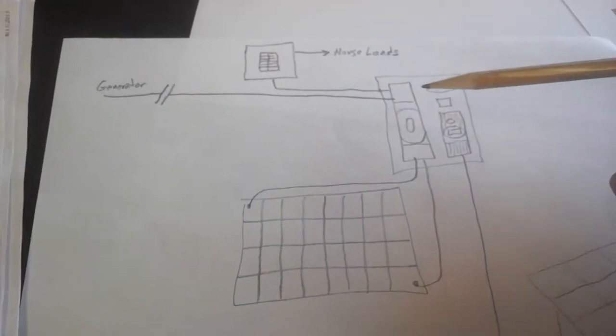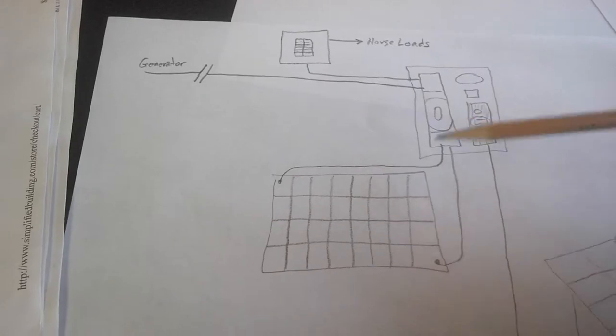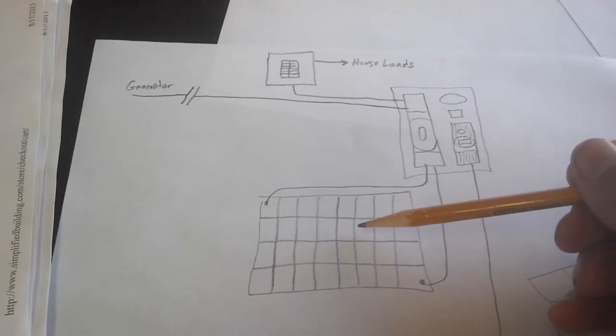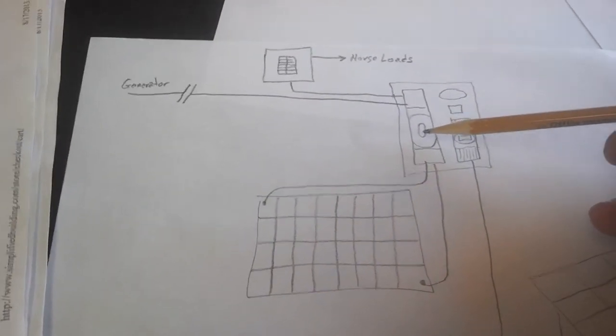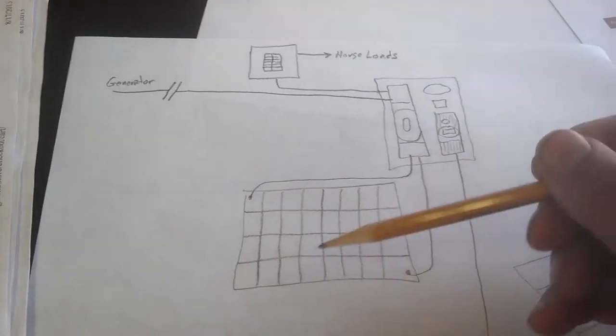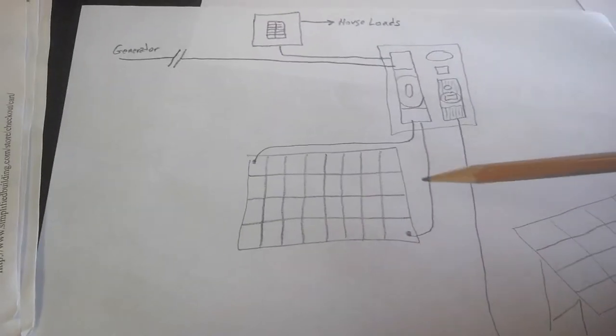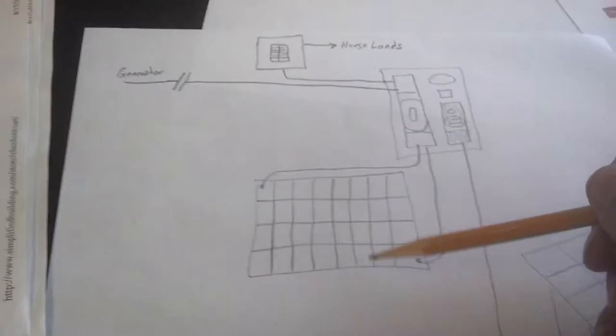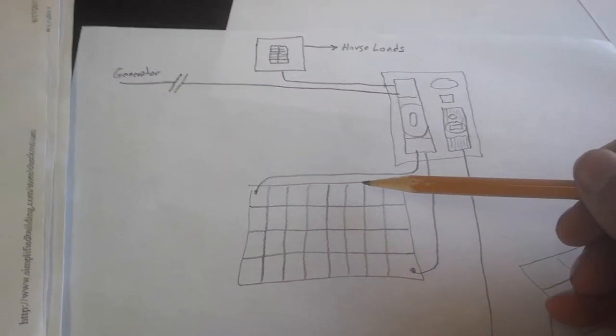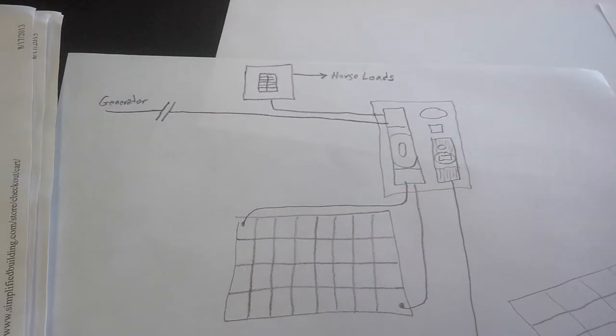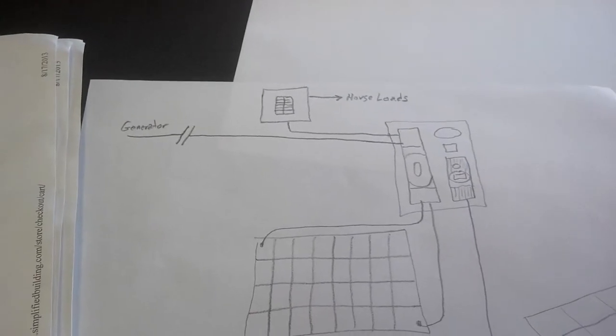So when the inverter is drawing the most, we want to keep the distance between the battery bank and the inverter as short as possible, because we don't want to lose anything there, especially on the low voltage side. So that's why we've got the beefy wires there. And instead of buying these jumpers pre-made, which we could have done, we saved more than half the money by planning on building them ourselves.